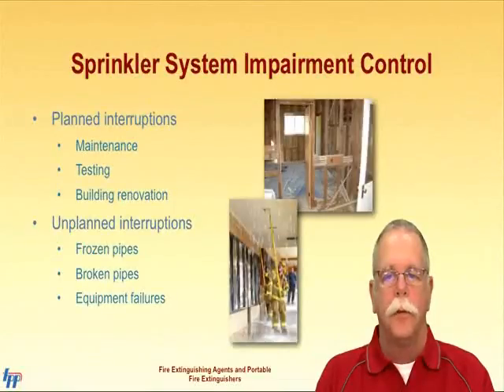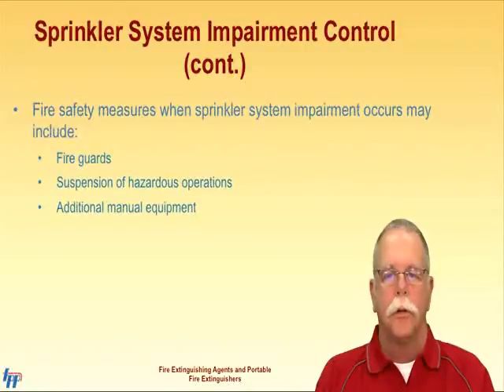For a sprinkler system to be effective, it must be in service continually with limited interruptions. Service interruptions or impairments can be broken down into planned and unplanned interruptions. When service to a sprinkler system is interrupted, countermeasures must be put into place to make sure the safety of the occupants and occupancy is not compromised. The actions to be taken during interruptions are also guided by NFPA 25, local ordinances, or fire codes.